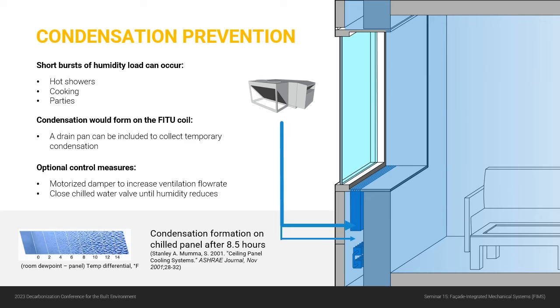So one example, you can use a motorized damper on your ventilation air. If you sense high humidity, you just increase the amount of ventilation air. Something else you could do with that is when you sense low humidity, you can reduce your ventilation air. So there's advantages to doing that. You can also do something like just closing the chilled water valve if you sense that humidity is getting too high.